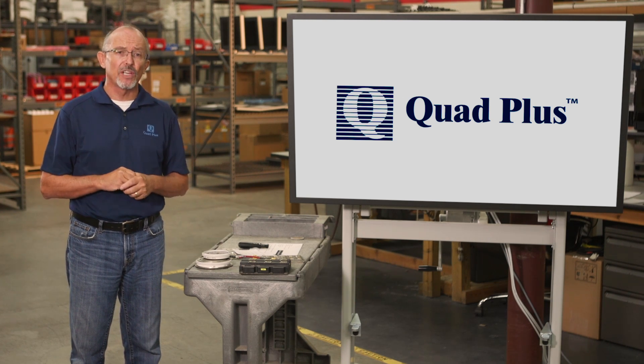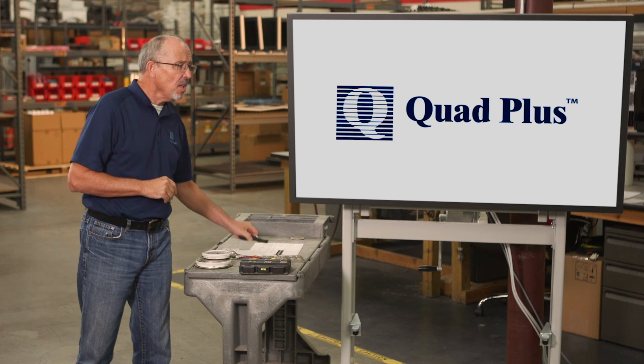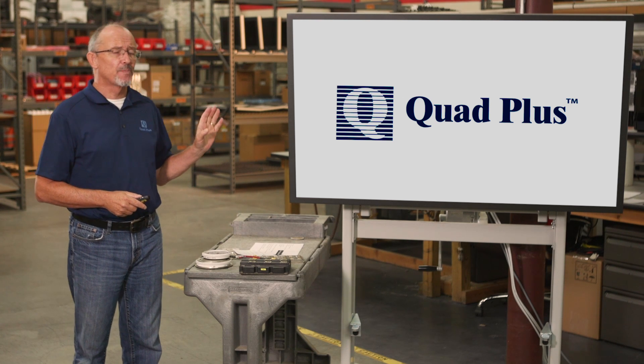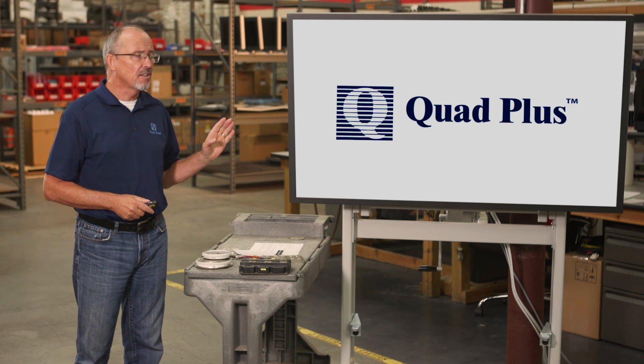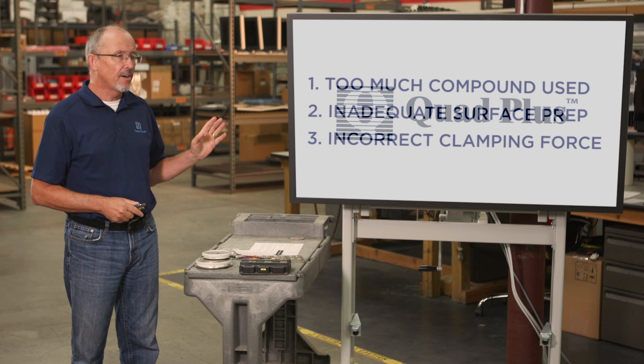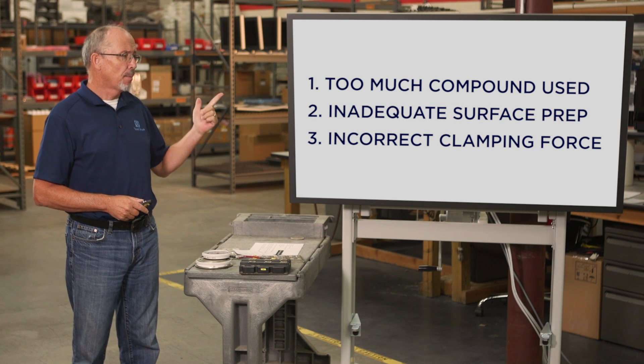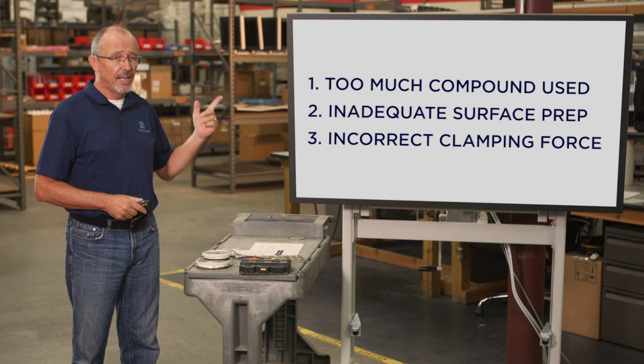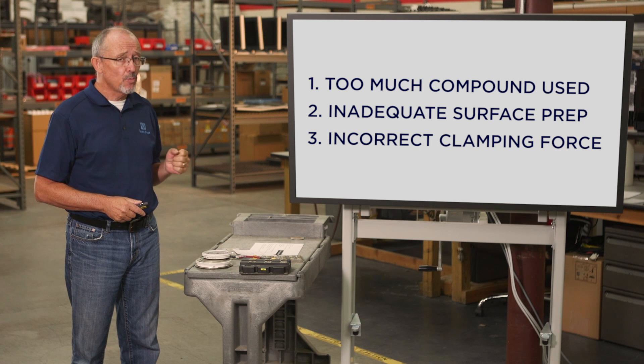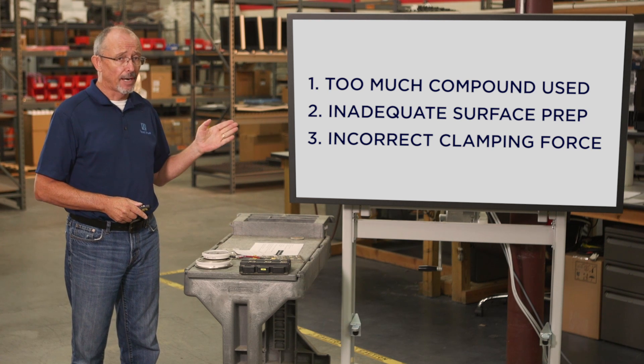Now let's address the second part of the question: what tips do I have for replacing semiconductors? The most common errors we see in the field are: number one, too much compound used; number two, inadequate surface preparation; and number three, incorrect clamping force.